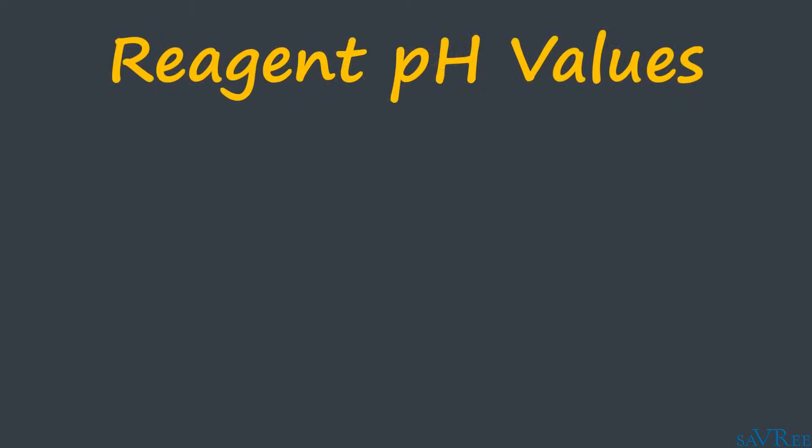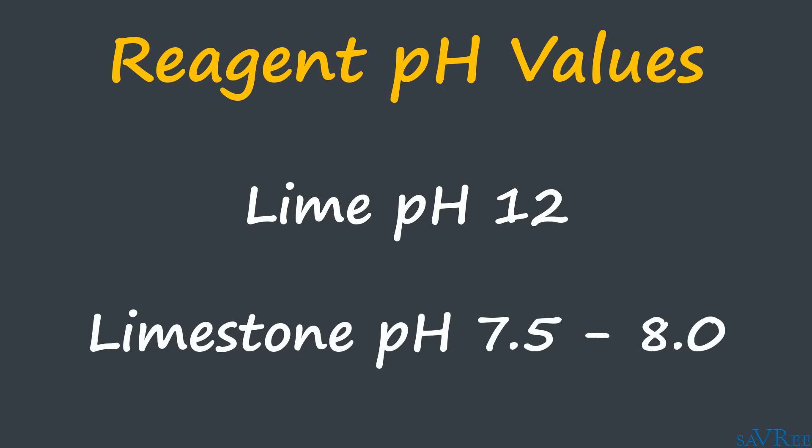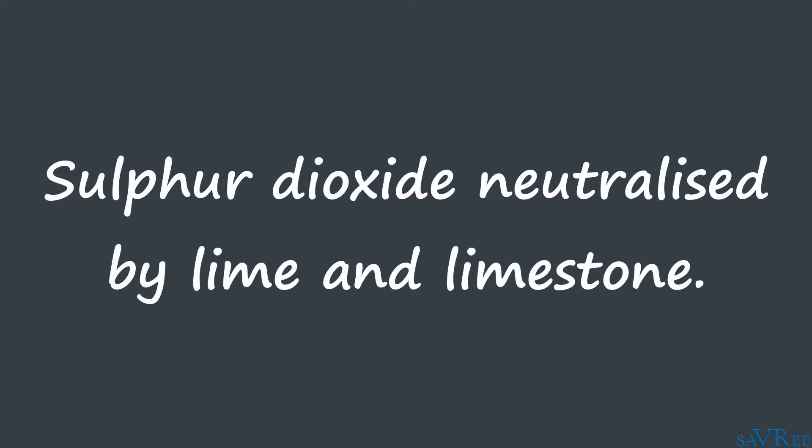Lime has a pH of about 12, so it is very alkaline. Limestone has a pH level slightly above neutral, somewhere around the 7.5 pH range. By mixing the alkaline limestone or lime with the sulfur dioxide gas, we bring up the pH level of the sulfur dioxide gas and bring it closer to seven. Once we've done that, we've neutralized the gas and we can dispose of it by selling it or perhaps sending it to a landfill site.